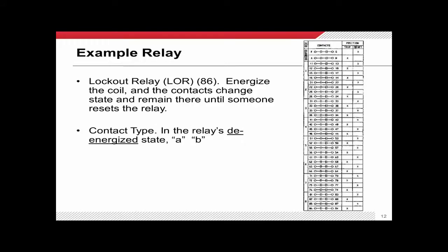Now, there are a couple of types of contacts within a typical lockout relay. Specifically, they're the normally open contacts that you'll use to trip devices, perhaps to send transfer trips, and for a function that's known as breaker failure initiate. But there are also B contacts, which are normally closed, and those are used to supervise closing of circuit breakers. If a circuit breaker has been locked out, you don't want to inadvertently have it close back into what would presumably be a fault in a live condition.